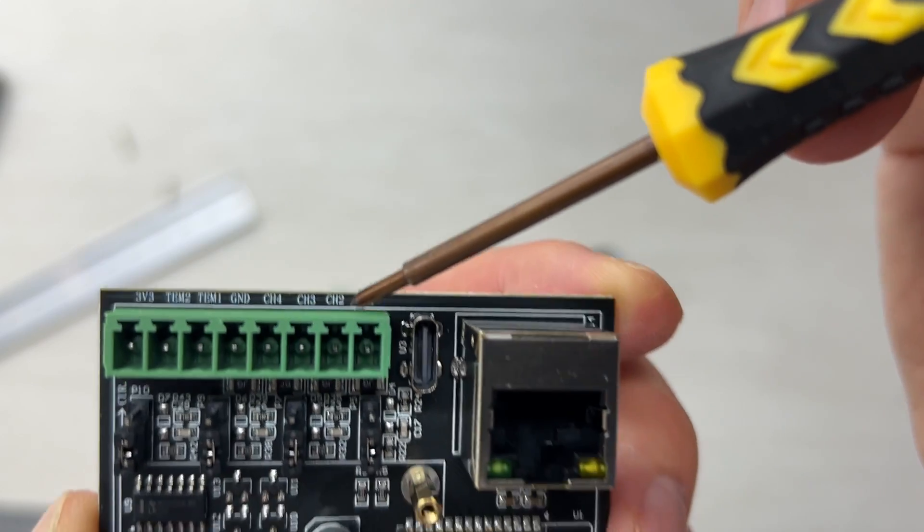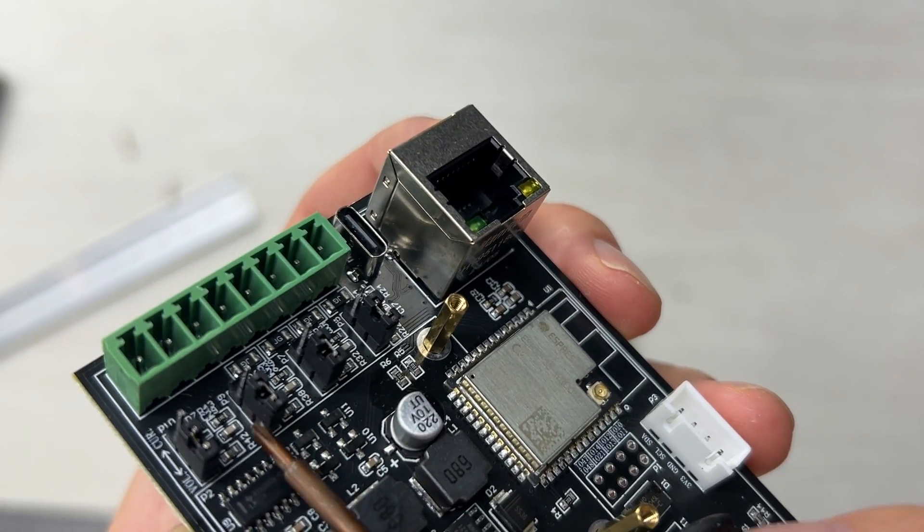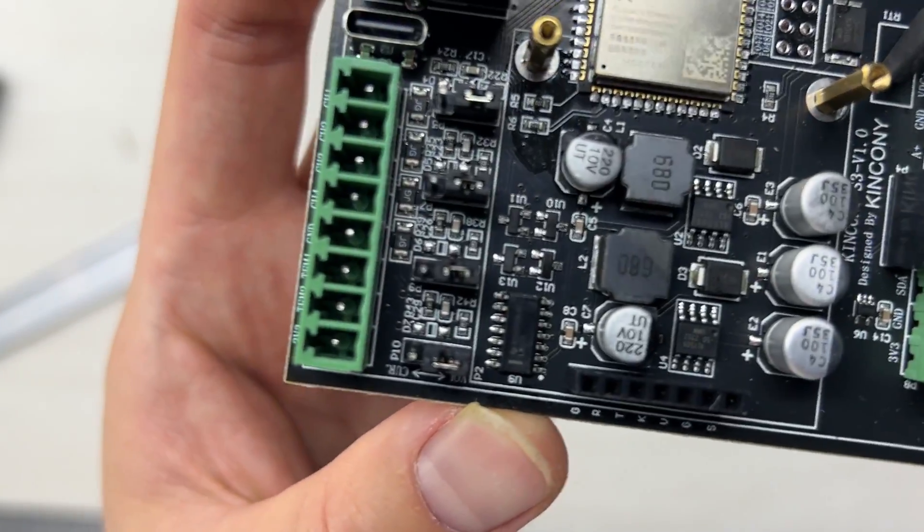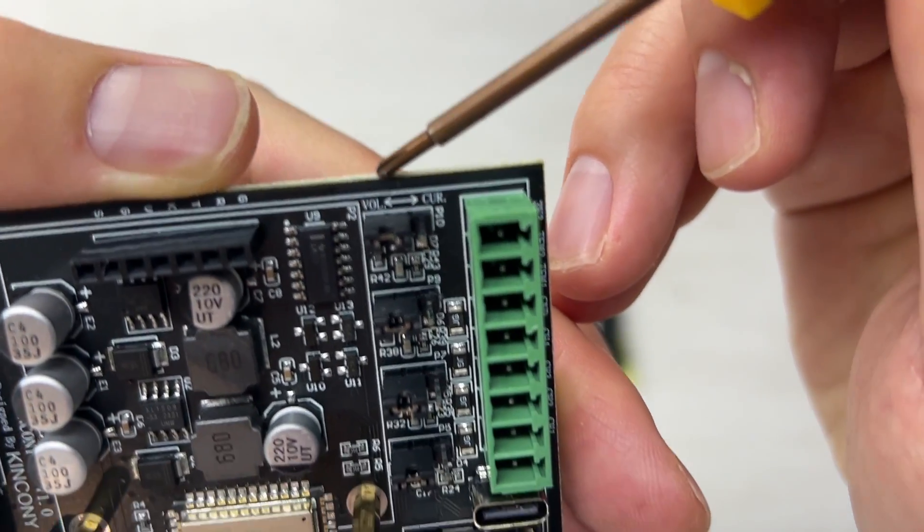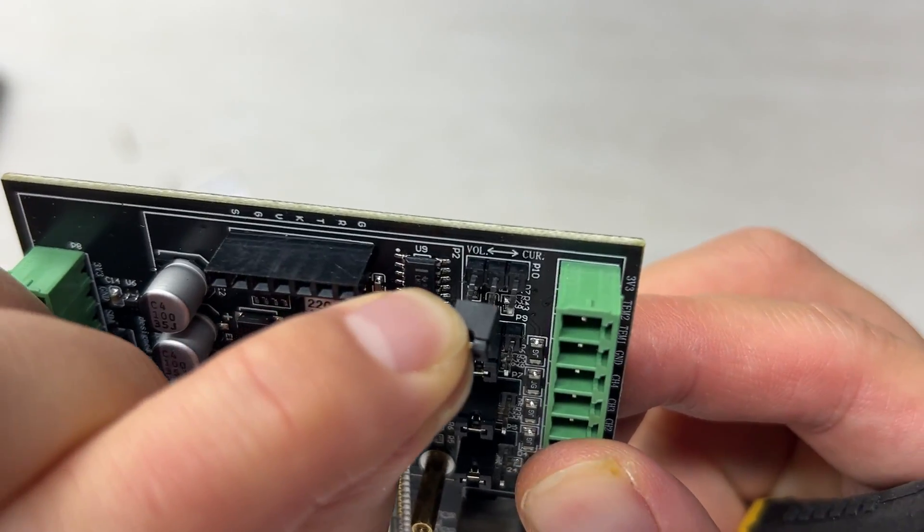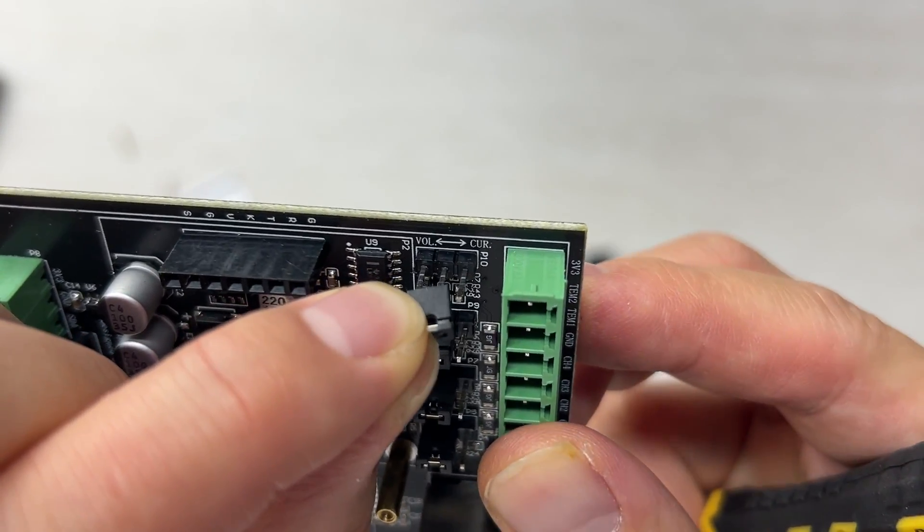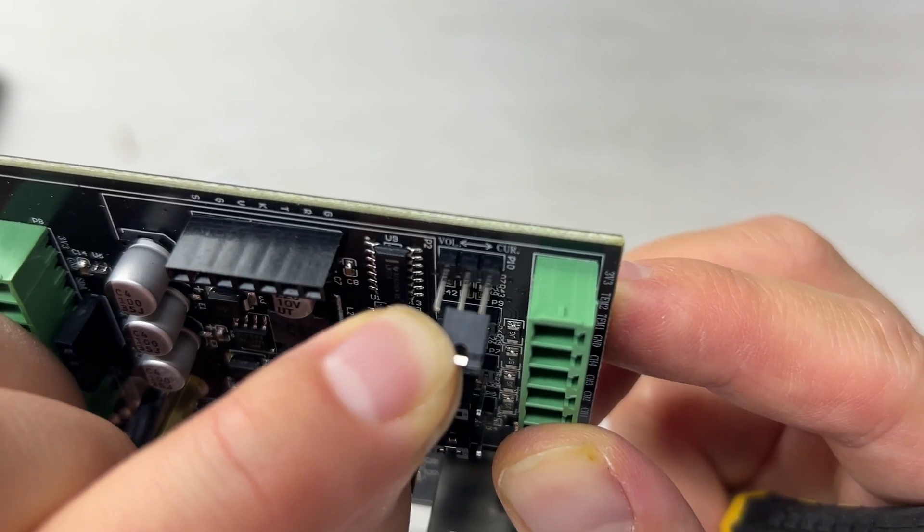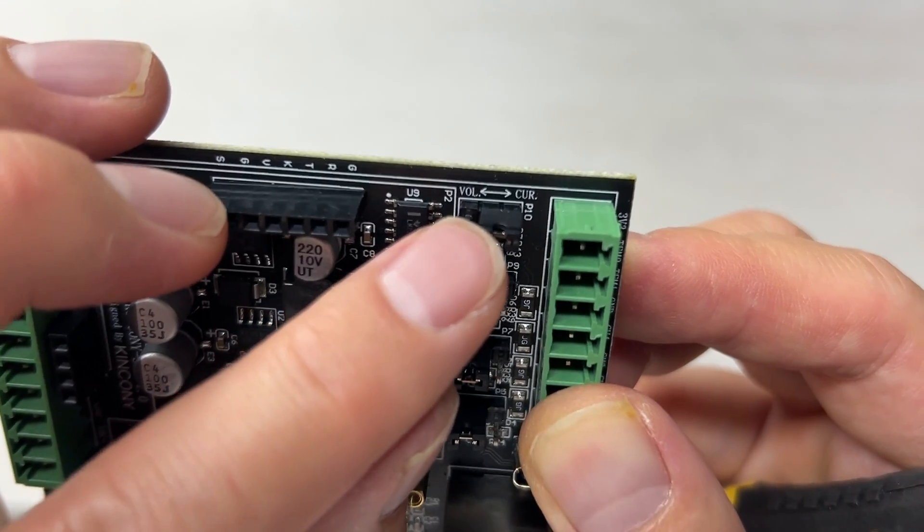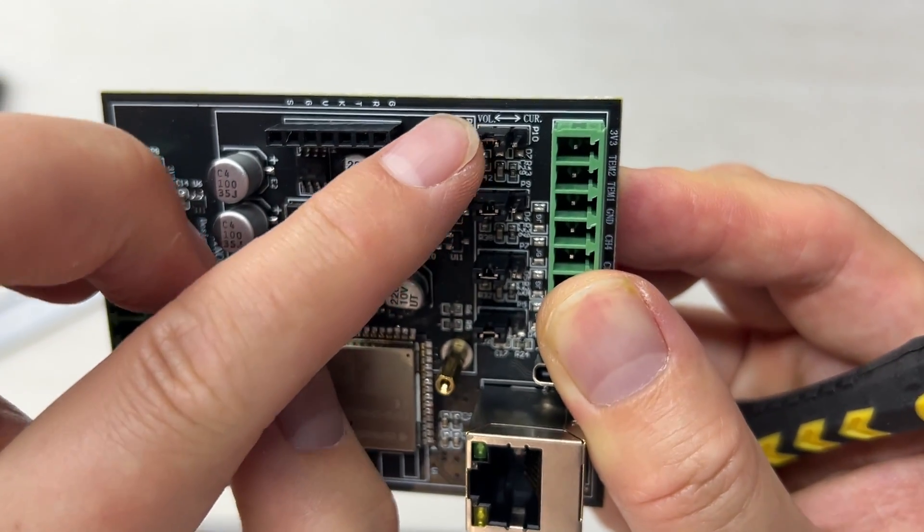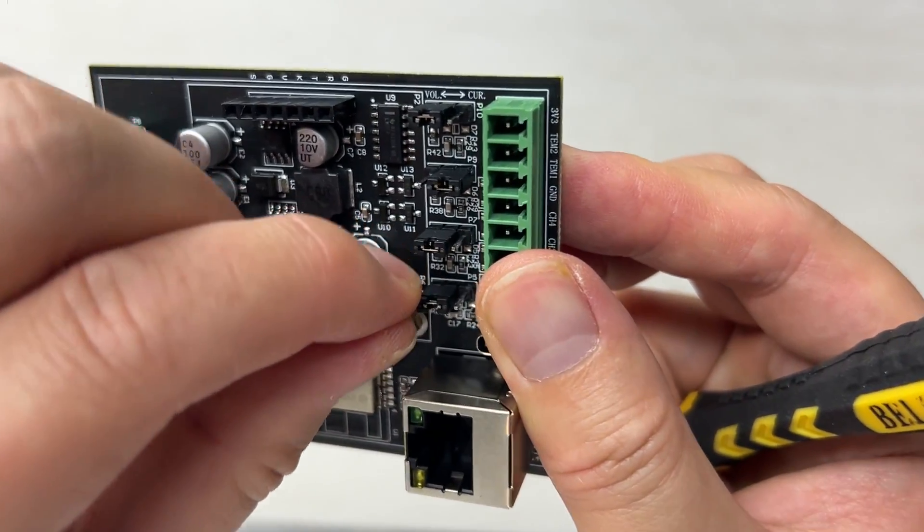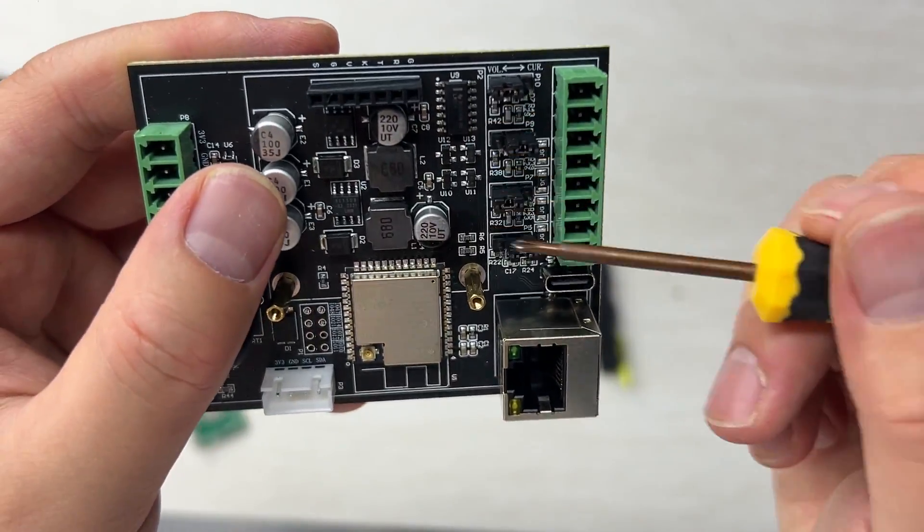We have designed four jumpers for the four analog inputs. You can change or set whether the analog is for voltage signal or current signal. At the left, that is DC 0 to 25V voltage sensor. If you set at the right, you can connect 4 to 20 mA analog sensor. This can be changed for different channels independently - for example, the first channel is voltage, the second is current, the third is voltage, or the fourth is current.